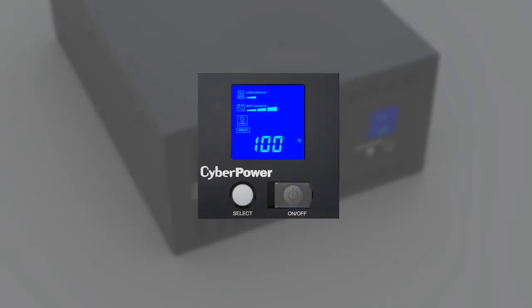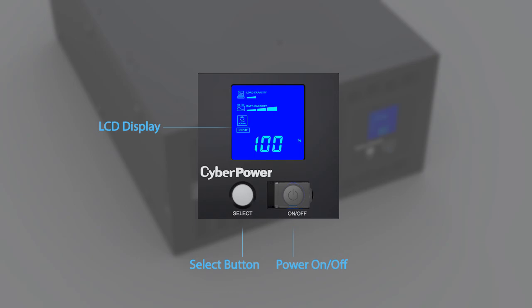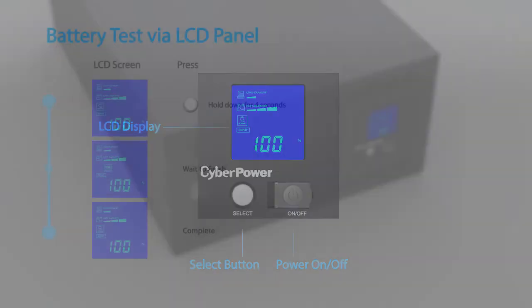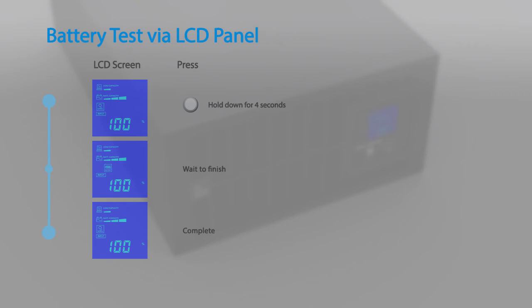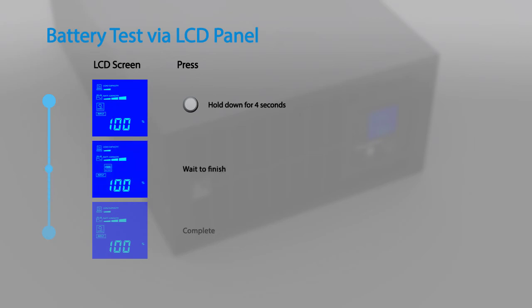You may run the battery test by using the LCD panel. This video will demonstrate using the buttons on the LCD panel to configure the UPS settings. To perform a battery test via the LCD panel, hold down the select button for four seconds during line mode. The test will run for a few seconds and then return to normal operation.